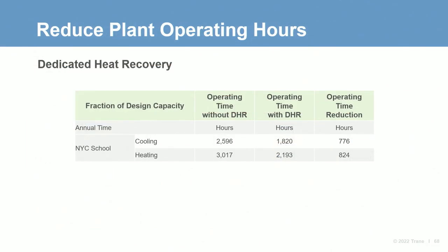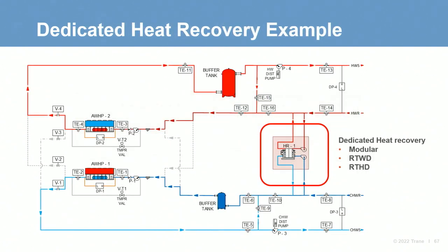Indeed. A dedicated heat recovery chiller is simple to apply between the two distribution loop return pipes. Keep in mind that a heat recovery unit can only move energy from one distribution stream to the other. Proper sizing of the heat recovery chiller is critical to the cost-effective design and selection of the system. The amount of energy that can be transferred between the loops is limited to the lower of the two loops' loads at any moment in time. With a properly sized heat recovery chiller, we have the opportunity to downsize the expensive air-to-water heat pump plant and right-size the equipment for its intended use. The end result is a more cost-effective electrified solution that still meets the needs of the customer.